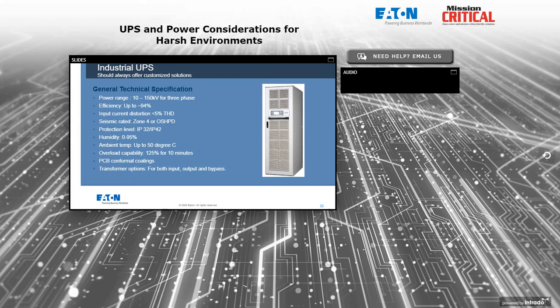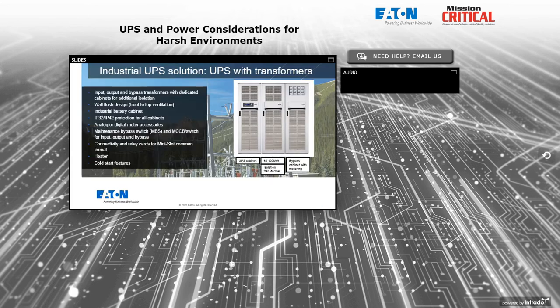It is common in this industrial world to see a specification that says thou shalt have galvanic isolation in the source that feeds this critical device. That means a transformer is going to be necessary, whether it's in the UPS or supplied separately. So UPS systems with transformers, they can be placed on the rectifier input, final output, the bypass input, any combination of the above. In some cases that'll require lineup and match cabinets. In other cases, the transformer can be supplied in a typical gray industrial enclosure, make sure it matches the site conditions for NEMA rating or IP rating.